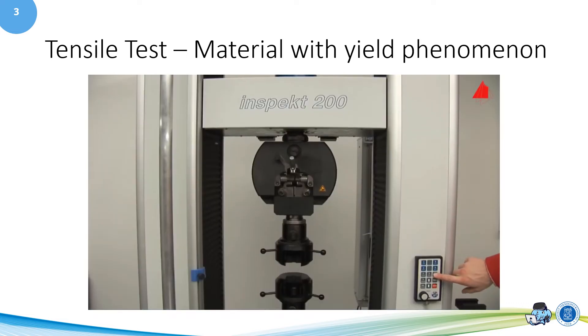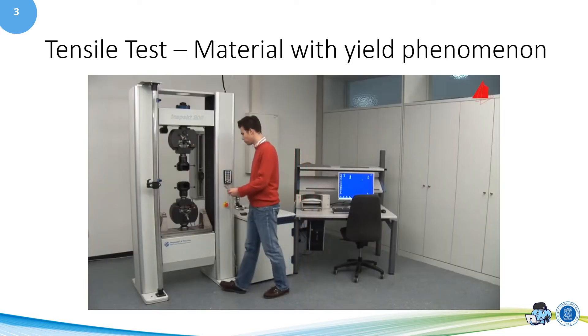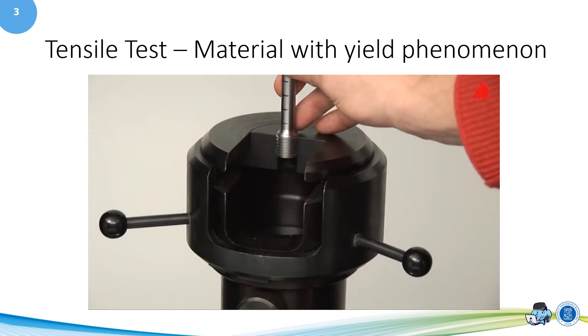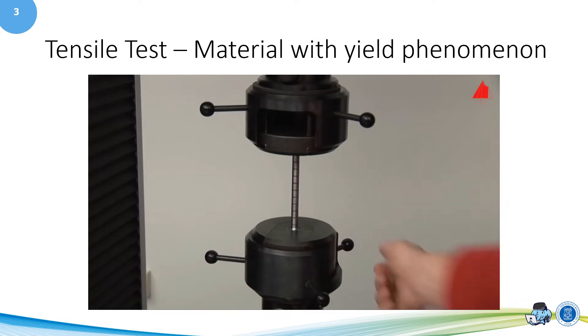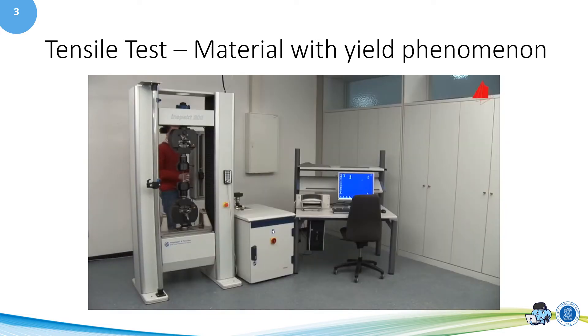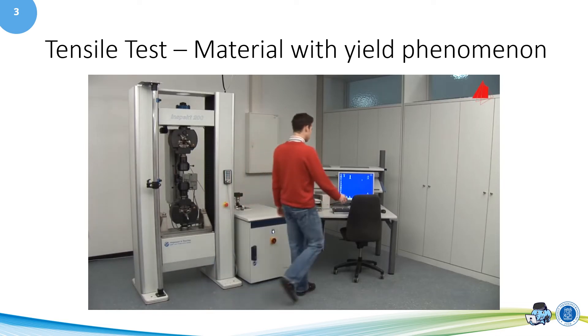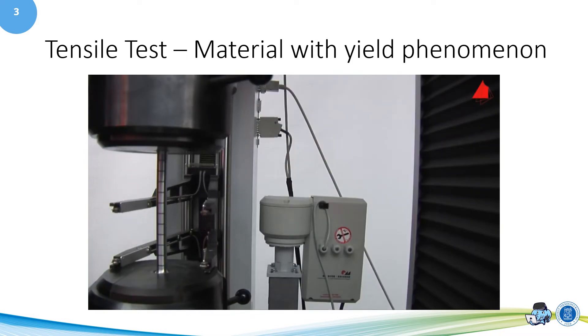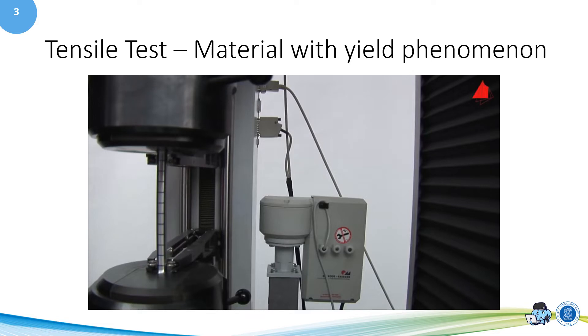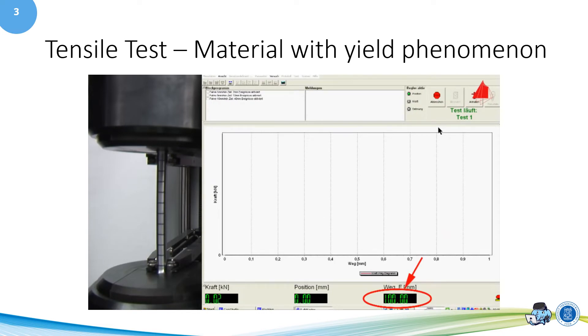Using a hand control, the tester moves the upper crosshead into its correct starting position. Now, he can place the threaded ends of the test piece in the lower and upper grips of the testing machine. In the next step, he swings the extensometer into its working position and checks that everything is correctly prepared. Then, he selects all necessary testing parameters on the control computer. The test starts and the extensometer's sensor arms are carefully pressed onto the test piece. The gauge length can be measured throughout the whole tensile test. The gauge length is displayed at the bottom right-hand corner of the screen. At the beginning, it amounts to 100mm.